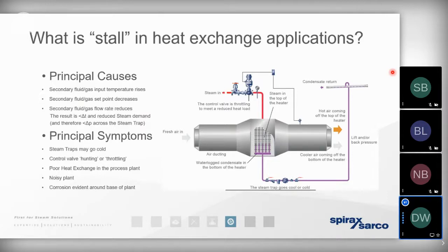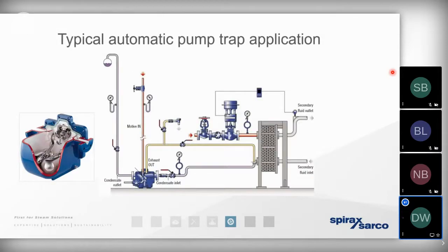Something that we refer to as stall, and something that is very, very common in heat exchangers using steam, especially if they can be using steam at relatively low pressures and temperatures for a certain period. The good news is we can calculate when stall is likely to occur, and we can also protect against stall from occurring. So when we've got the steam that exists at a nice high temperature and nice high pressure, with enough motive energy in the steam, so that condensate can be managed by passing it away across a typical float trap. But we can also use an automatic pump trap.